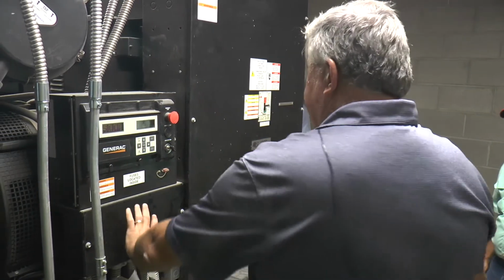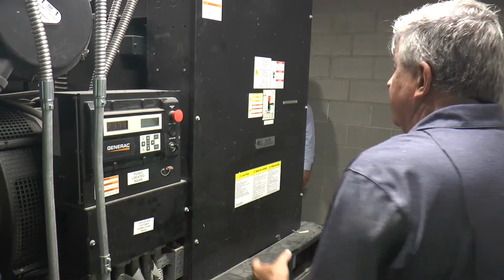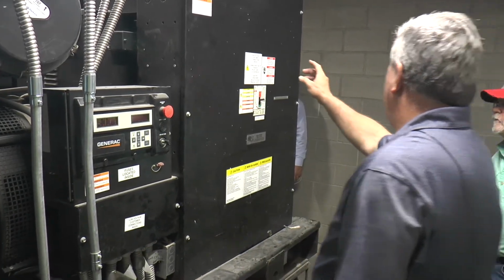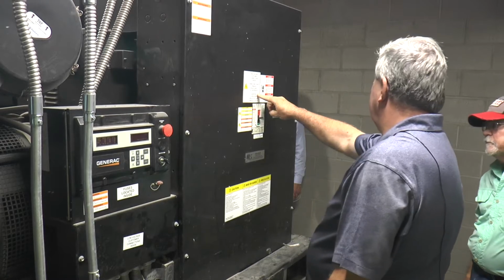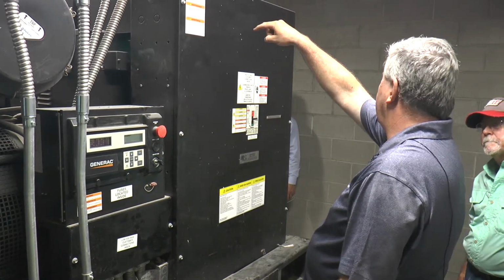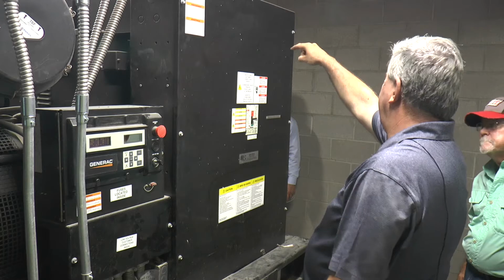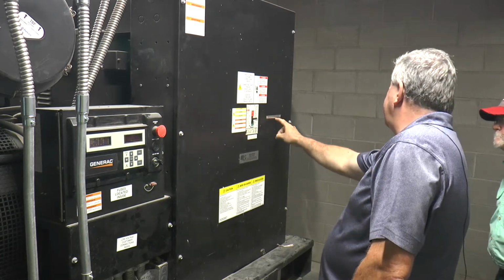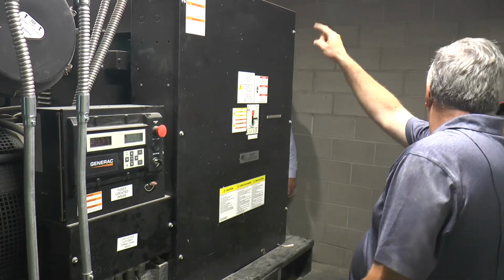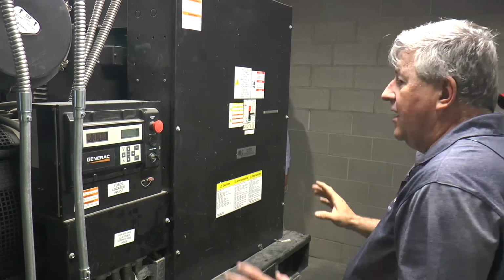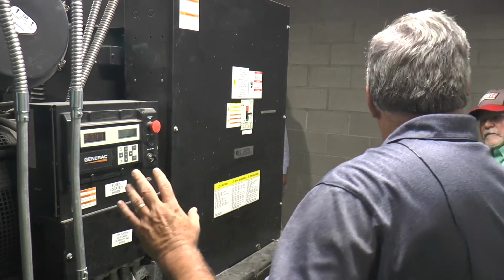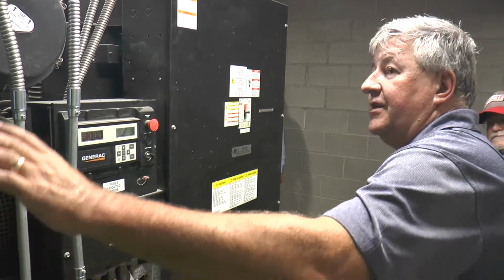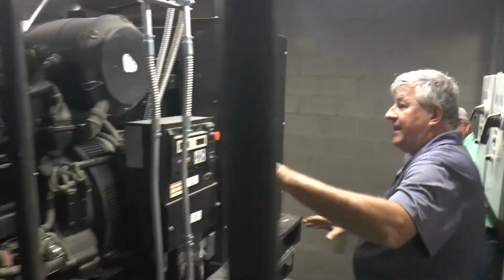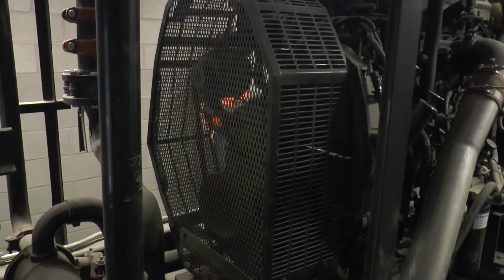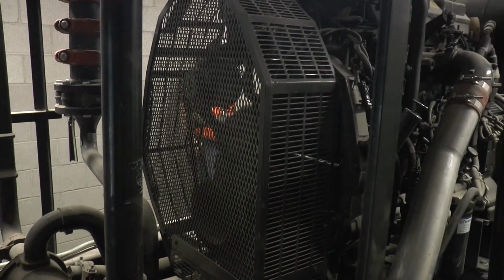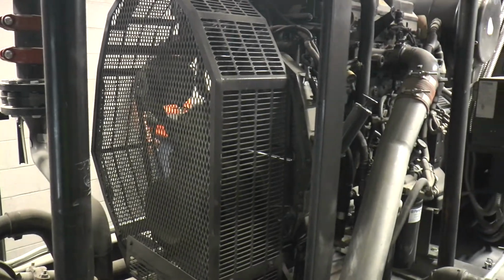All the low voltage customer connections are brought into this area. Generators equipped with 3 breakers, 1 breaker here for equipment, 1 breaker on the other side for fire pump, and I think the other one, nope, pardon me, this is the fire pump feed. The other 2 are life safety and equipment. Okay. The engine also has a remote radiator. So on the front of this engine is a cooling system that basically takes coolant from the engine, transfers it to another medium, and then pumps it up to the remote radiator on the 3rd floor.